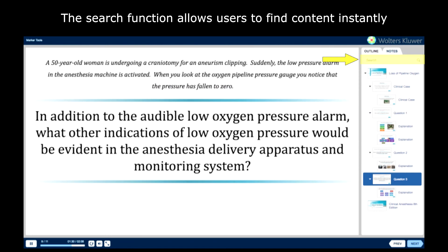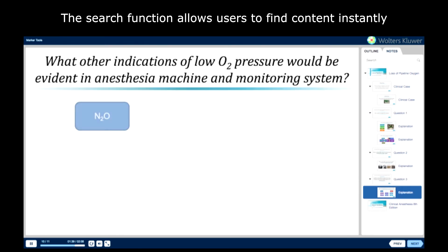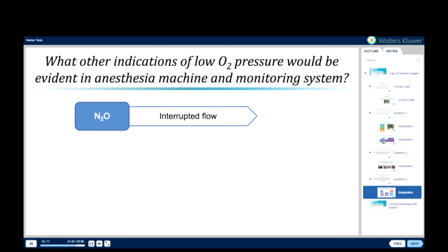In addition to the audible low pressure alarm, what other indications of low oxygen pressure would be evident in the anesthesia delivery apparatus and the monitoring system? If nitrous oxide is being used, its flow would be interrupted, provided the fail-safe system is properly working.